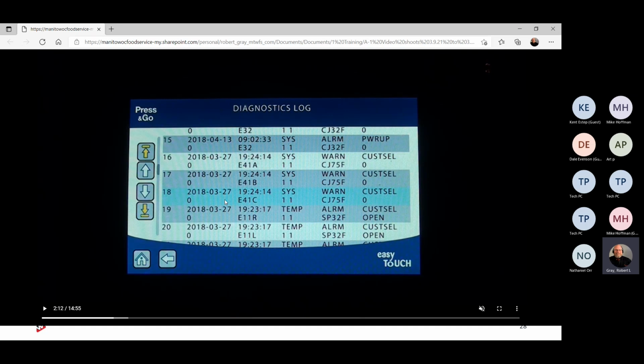For 41A, B, and C, it's going to be one of those scenarios. Bad contactor, not the right voltage coming into the unit, or no 3-phase power, actually I should say. And or one of your safety thermostats for each of your heating zones has opened up for that lane. So for A, B, and C, you're going to go in those 2 directions.